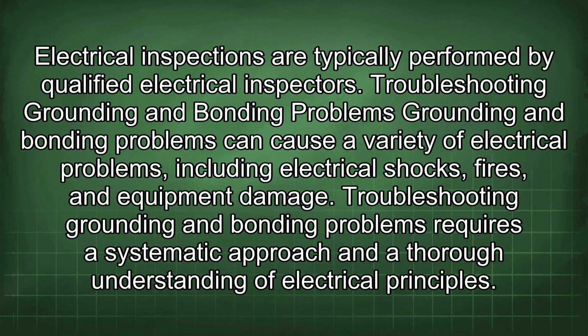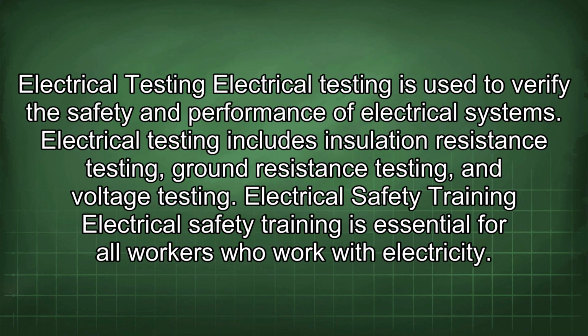Troubleshooting grounding and bonding problems. Grounding and bonding problems can cause a variety of electrical problems, including electrical shocks, fires, and equipment damage. Troubleshooting grounding and bonding problems requires a systematic approach and a thorough understanding of electrical principles. Electrical testing. Electrical testing is used to verify the safety and performance of electrical systems. Electrical testing includes insulation resistance testing, ground resistance testing, and voltage testing.